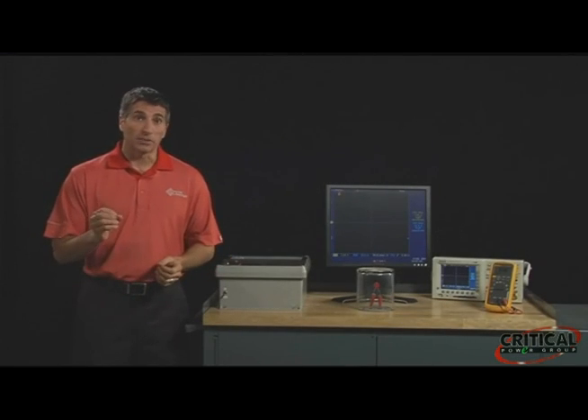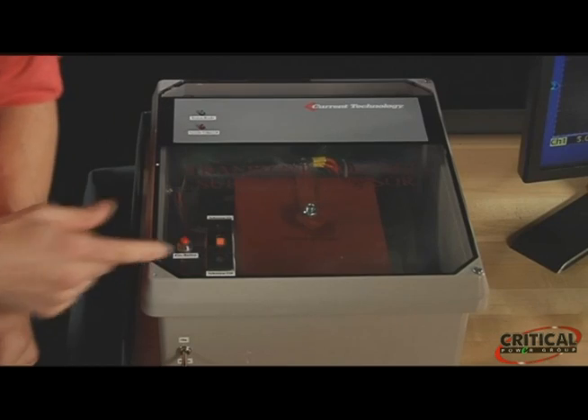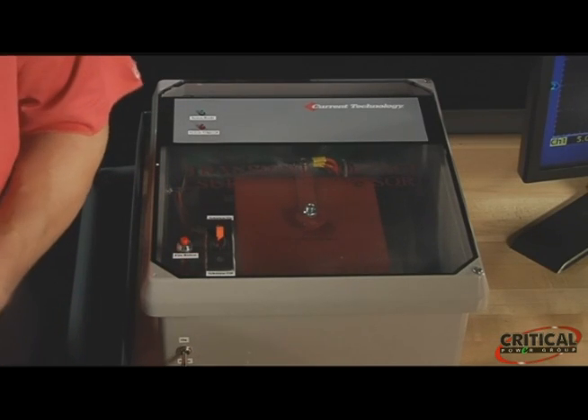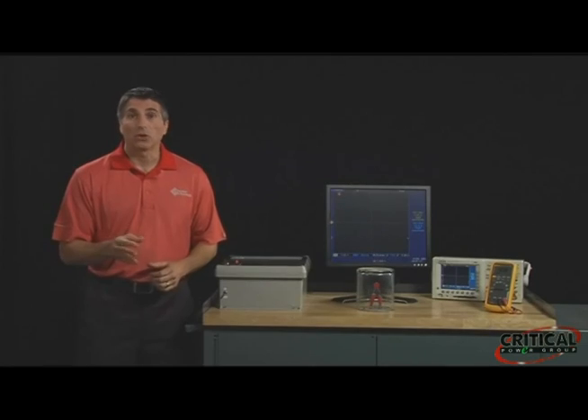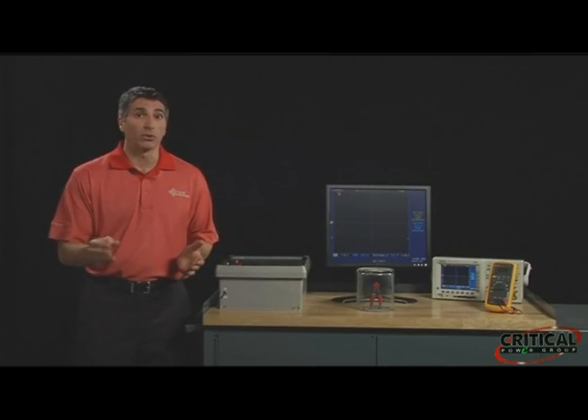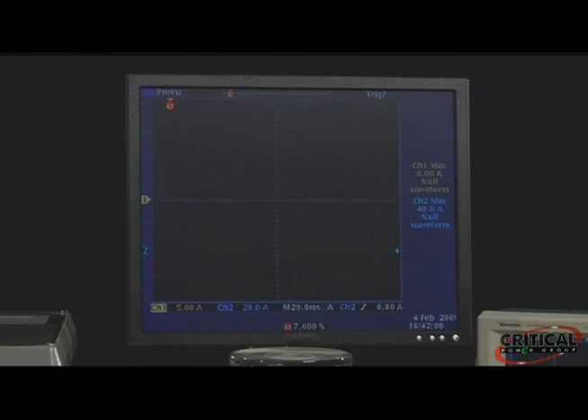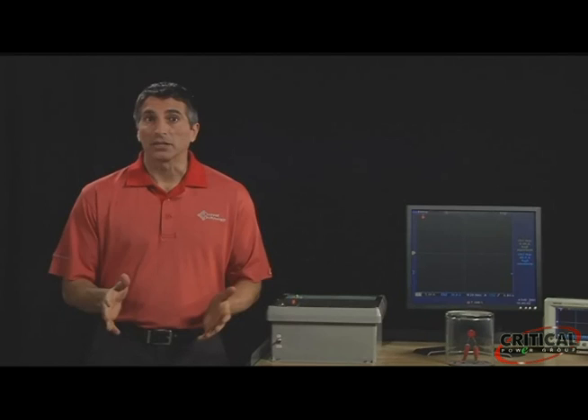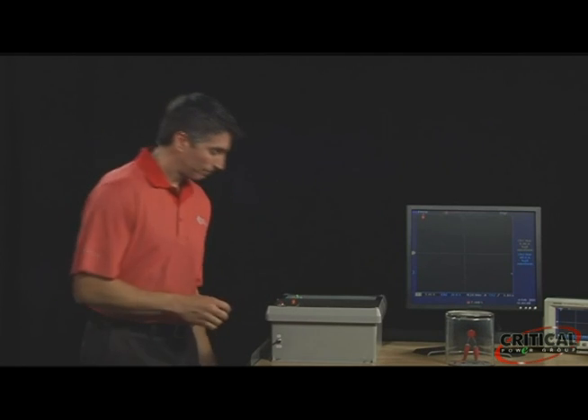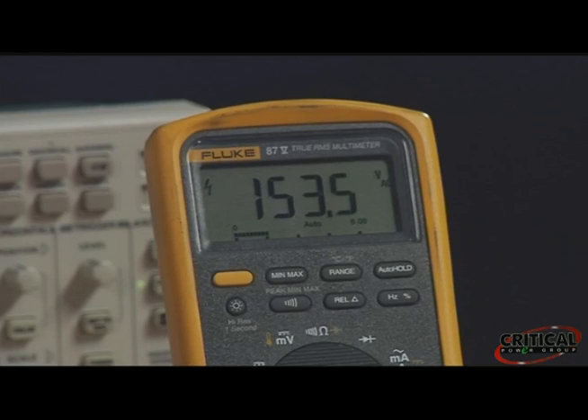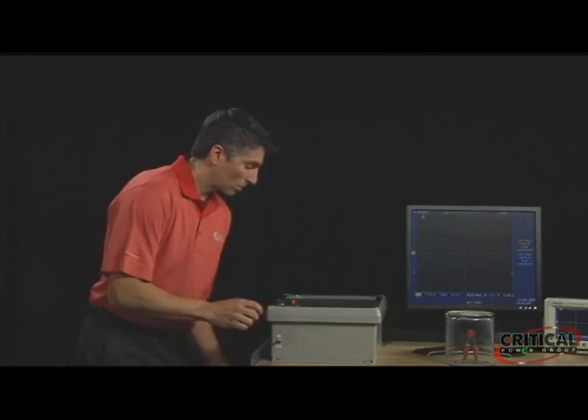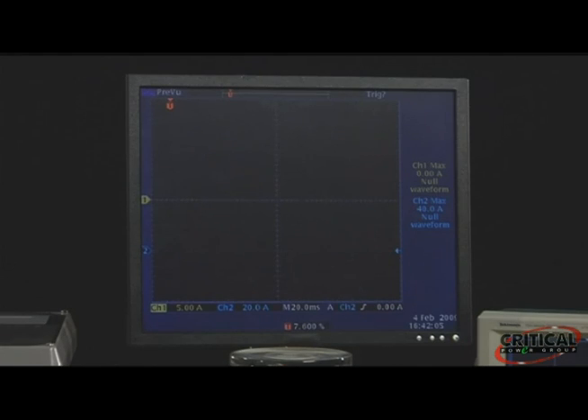This demonstration is very similar to the previous one, except for one difference. In this test, we'll add a selenium cell in parallel with the MOV. Our current transformers are set up to detect current flow through both devices. The current levels will be displayed on this monitor. We'll begin the test by subjecting the MOV and the selenium cell to a 30-cycle TOV at 150 volts. And we can see that neither the selenium nor the MOV did any clamping at that voltage. The downstream equipment would see the full extent of that power quality event.